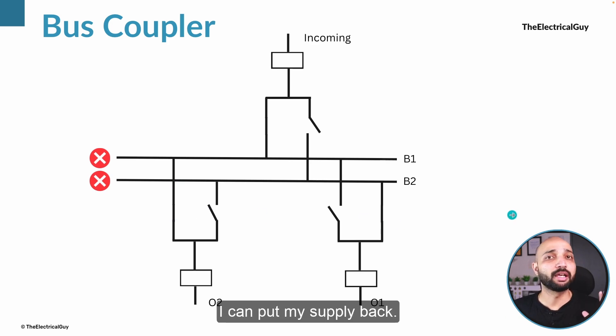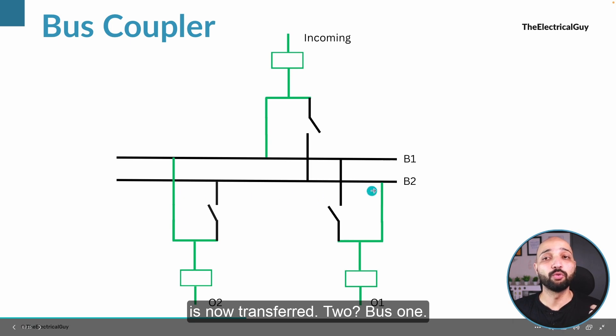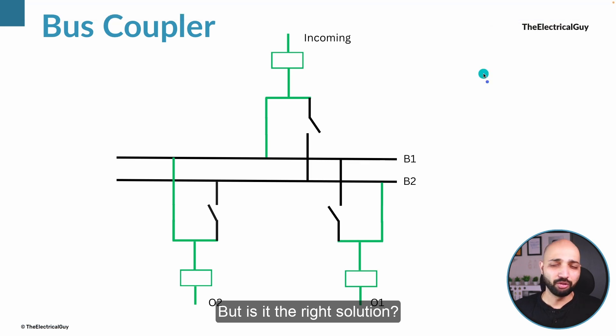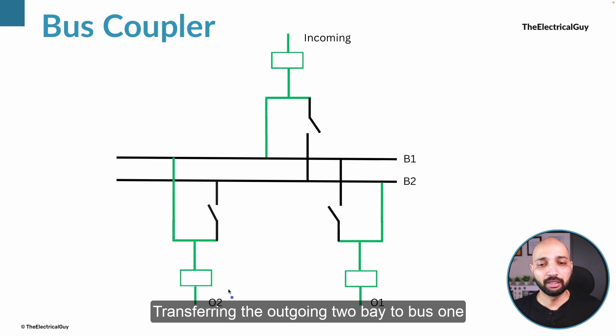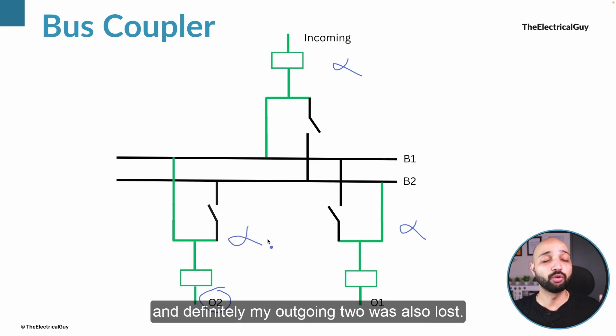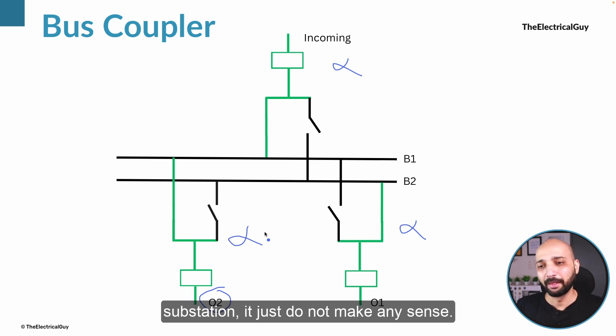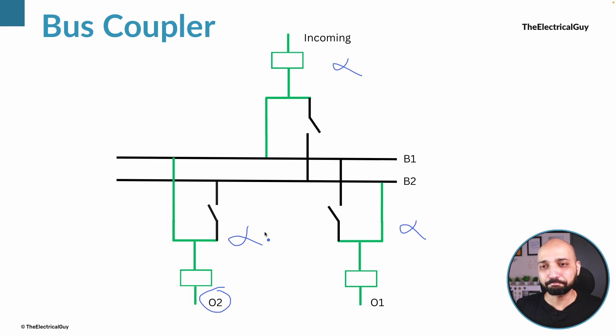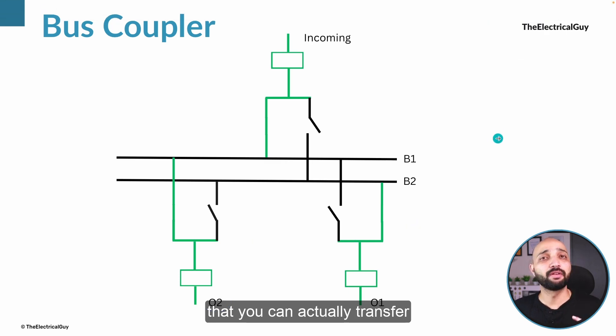Once that disconnector is closed I can put the supply back, and outgoing two is now transferred to bus one. But is this the right solution? The answer is no — because while transferring outgoing bay two to bus one we had to completely turn off the substation. The incoming was lost, outgoing one was lost, and outgoing two was also lost. It is of no use; it does not offer any flexibility. There is a better solution.